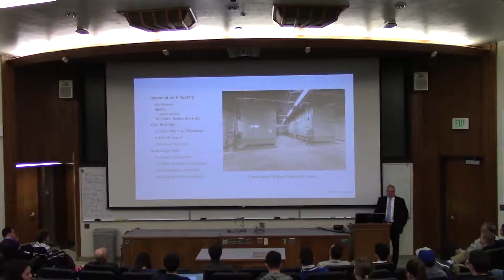Cogeneration starts with natural gas, goes into the gas turbines, and produces electricity and heat exhaust. The electricity was used to fuel or to operate the central utility plant itself, or we send electricity back to the grid. The electricity would also operate our electric chillers, which produce chilled water that then goes to the buildings. The heat exhaust goes to the heat recovery steam generation, which produces steam, which then runs heat exchangers that produce hot water that goes into the terminals and operates the steam-driven chiller that produces cold water that goes to the terminals. And that's all used for the HVAC systems in the terminal buildings. This is the heat recovery system.